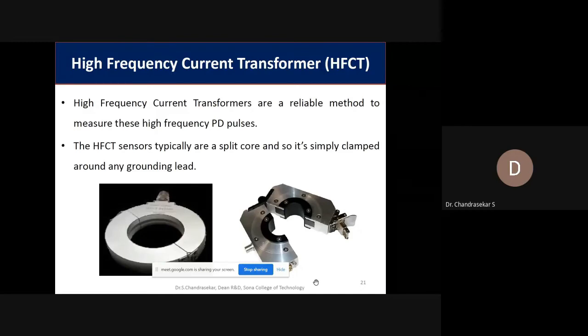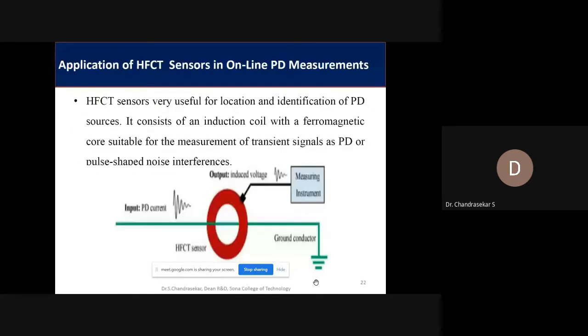So these are all the high frequency current transformers. This is a very reliable method for measuring high frequency PD pulses. There are also split core types available, and clamp types are also available. In any ground lead of the transformers or cables, if you connect this high voltage HFCT sensor, then you can easily measure the high frequency signals. Okay, so that is possible through these HFCT sensors.